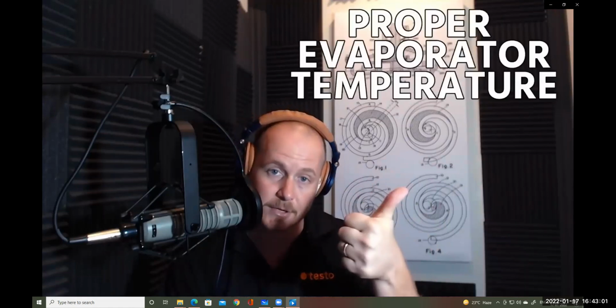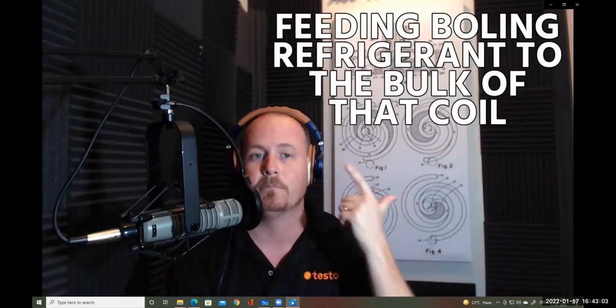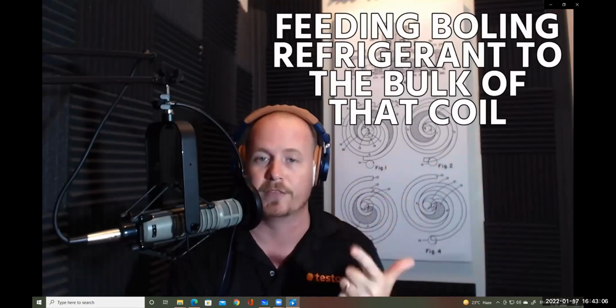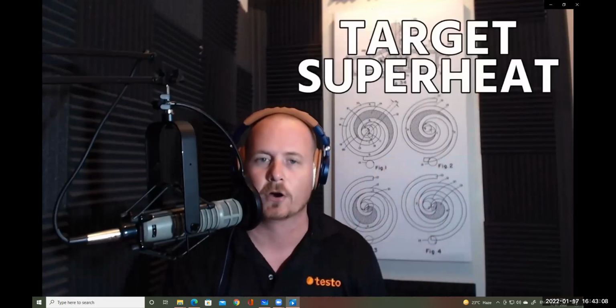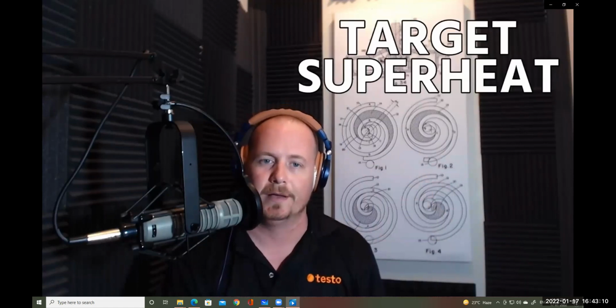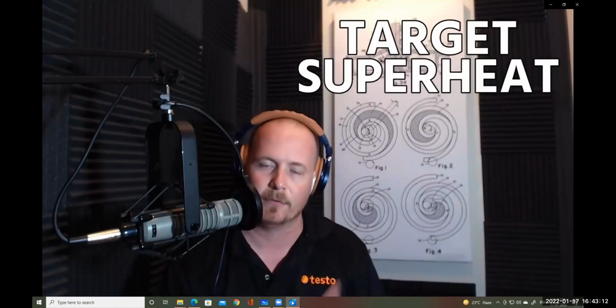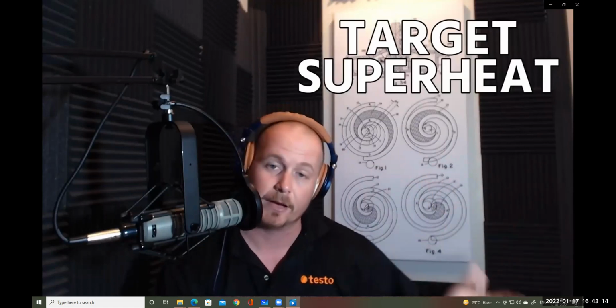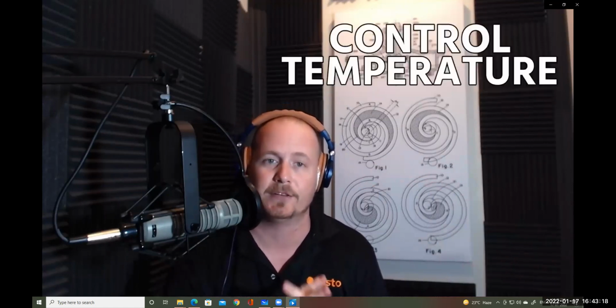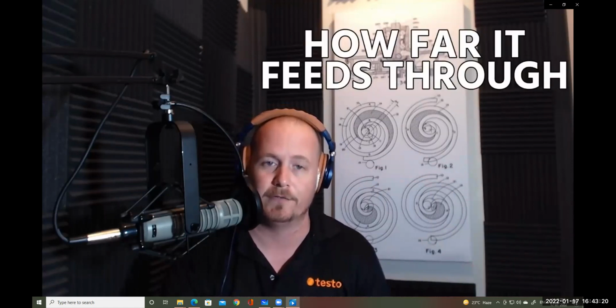So it's very important that we get all of the situations correct, so that we have a proper evaporator temperature, and so that we're feeding that boiling liquid refrigerant through the bulk of that coil till we hit what we call our target superheat, the point at which it's designed to become a vapor before it goes back to that compressor again, because that compressor is a vapor pump. What's the point here? The point is that we have to control that temperature, how far it feeds through.